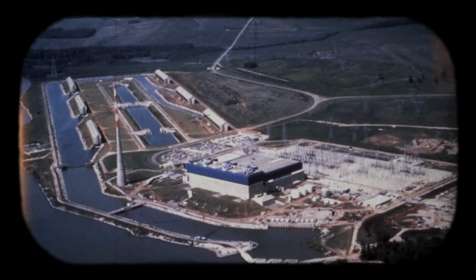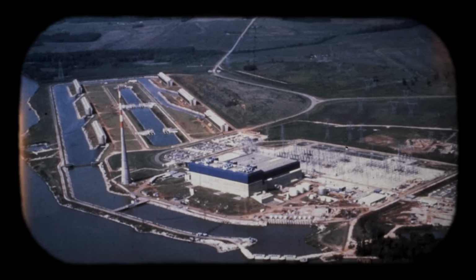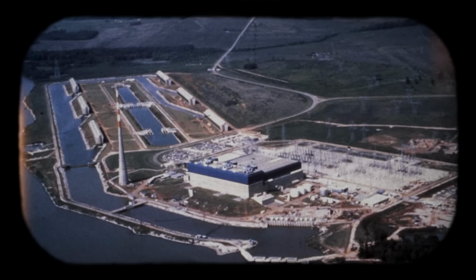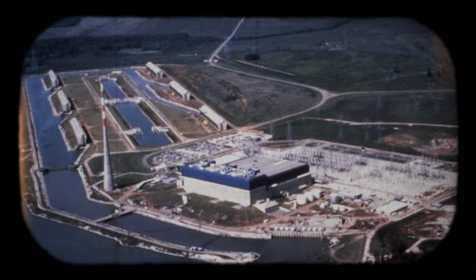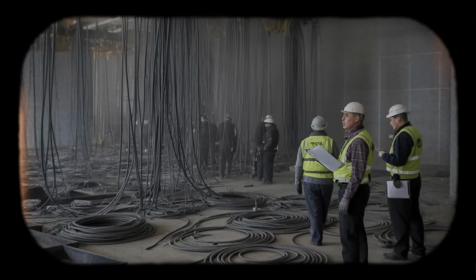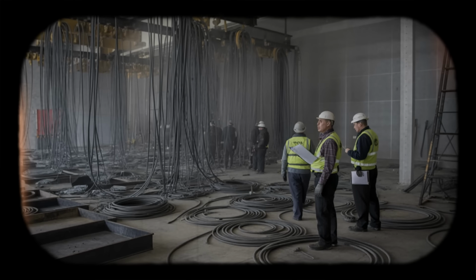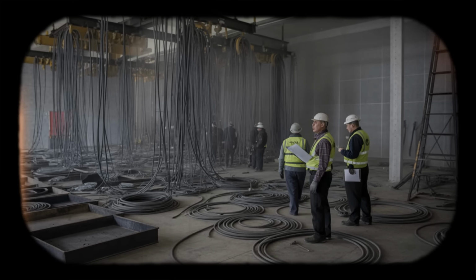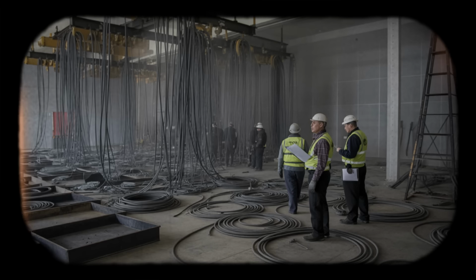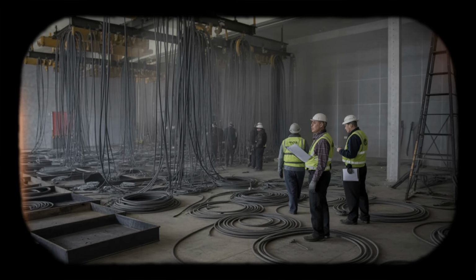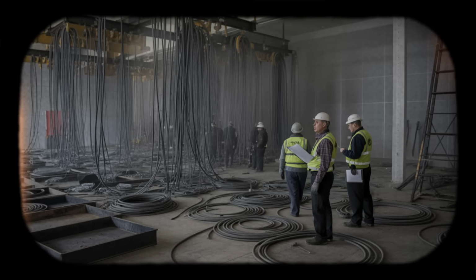The archival quote from TVA operations record states, "Field personnel were stationed at key pump locations to confirm operation by direct observation." This represents a fundamental change in operational mode. Nuclear power plants are designed for remote operation. Hundreds of sensors feed information to the control room. Operators make decisions based on instrument readings, not on direct visual inspection of equipment.